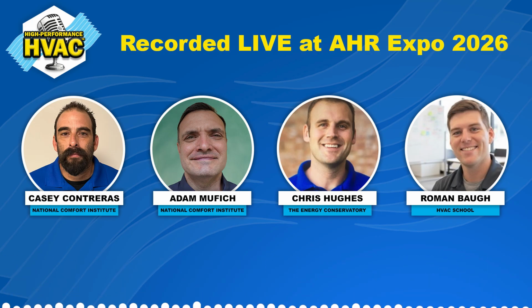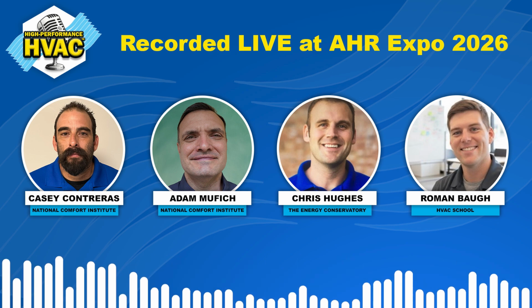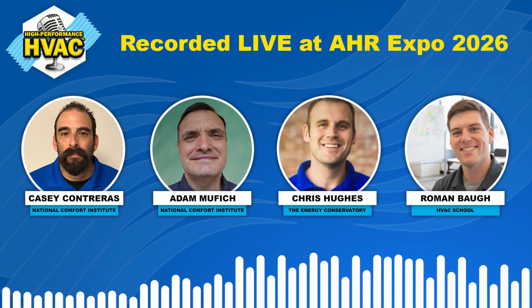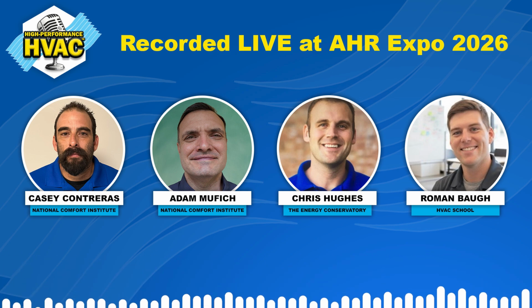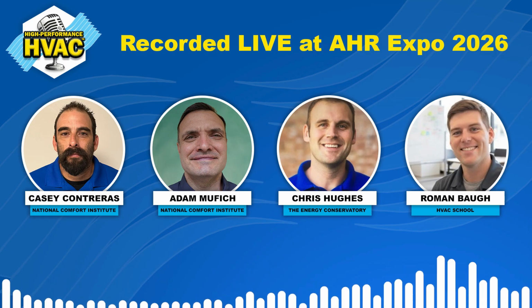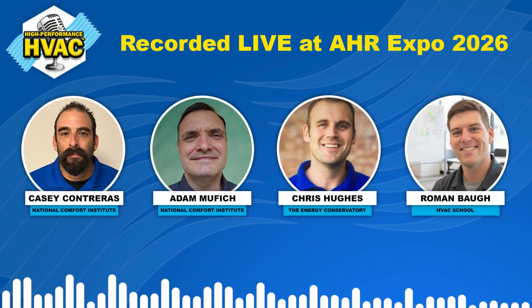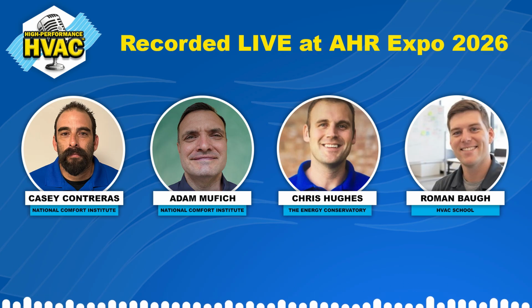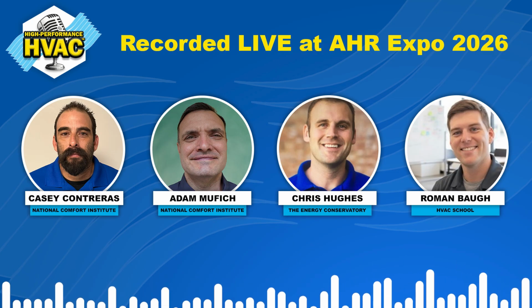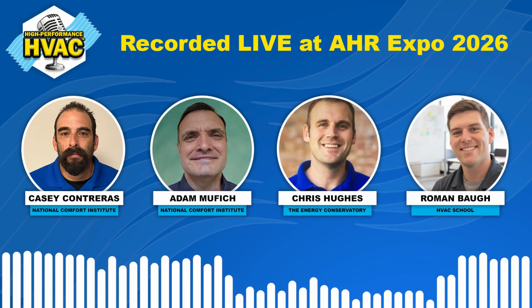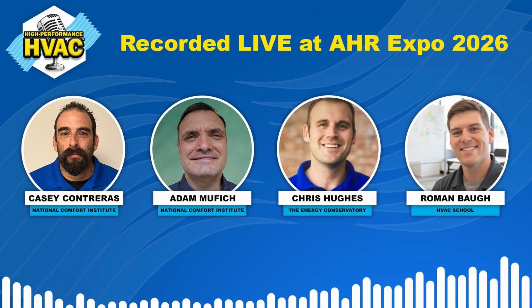So let's talk about EEV steps. What were you seeing on indoor and outdoor EEVs? Yes, outdoor EEV wide open. So my outdoor unit, which is an evaporator at the time, was starved. It wasn't getting enough gas. Yeah, it was trying to get more gas. It was wide open, and it wasn't getting enough gas. And then you saw the suction superheat climb.